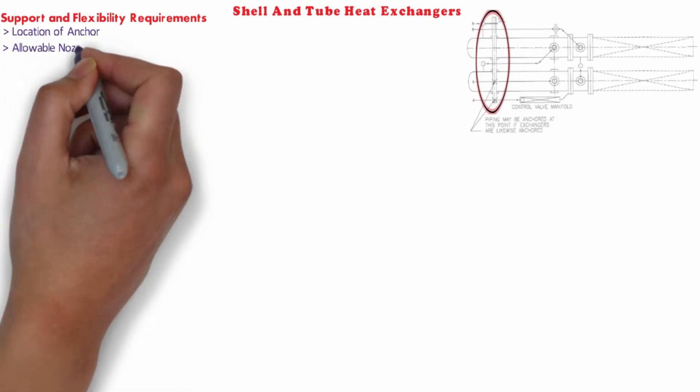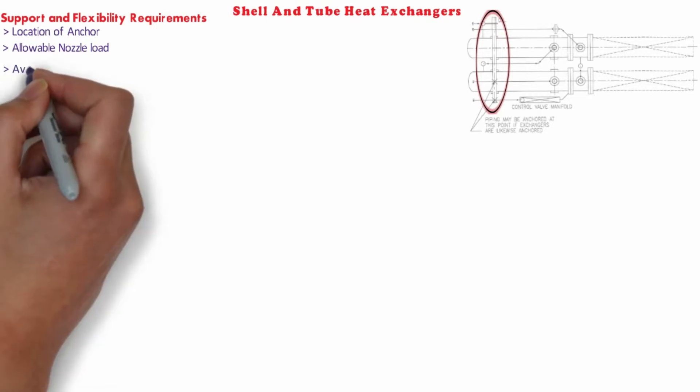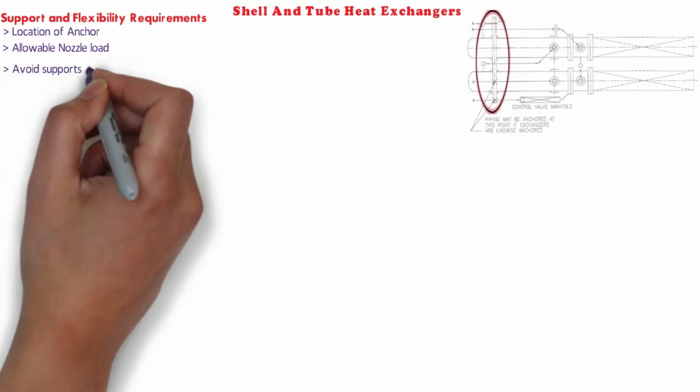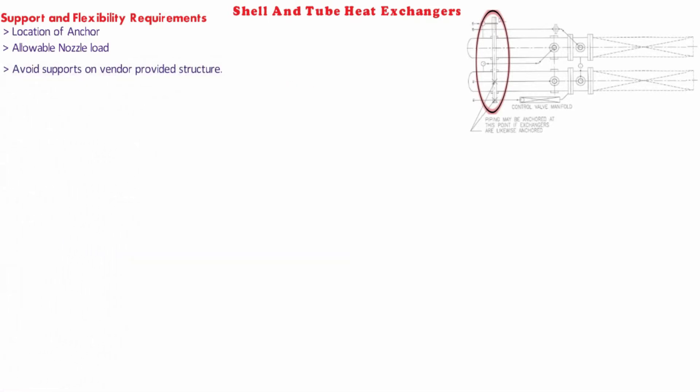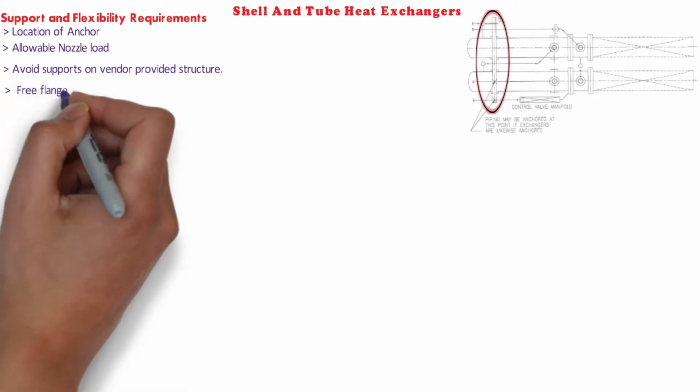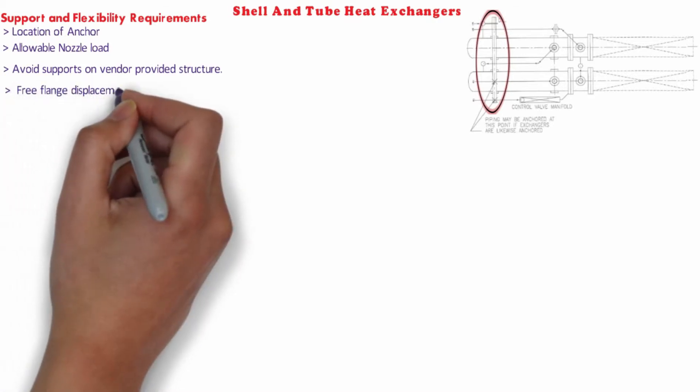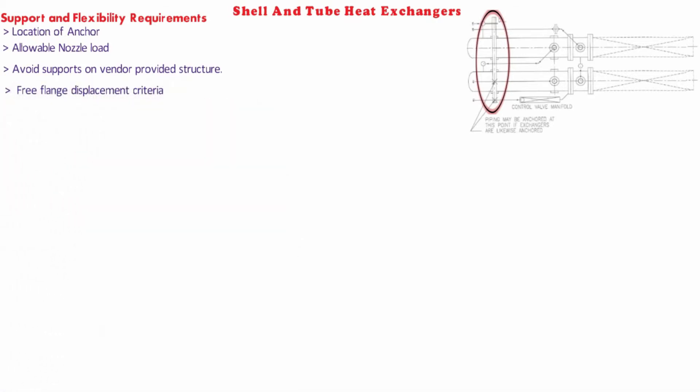Allowable nozzle loads. As per our standard nozzle loads of equipment, allowable nozzle loads should be provided to mechanical department at inquiry and inquisition stage of air coolers. Piping supports on vendor provided structures should be avoided. If any of the client specification mentions free flange displacement criteria, then supporting methodology shall be finalized accordingly at the initial stage of project.